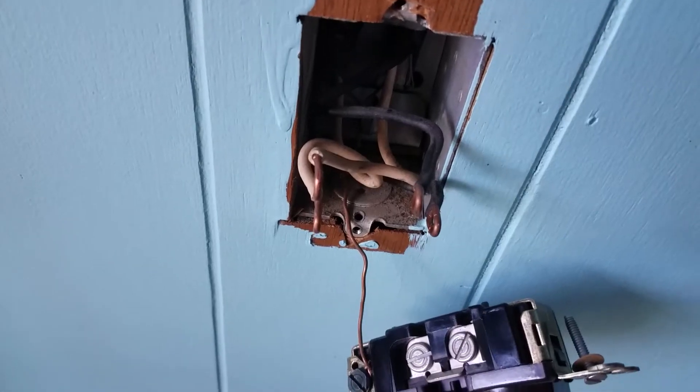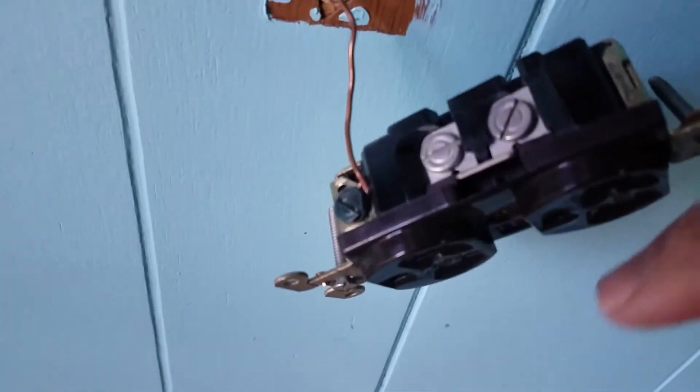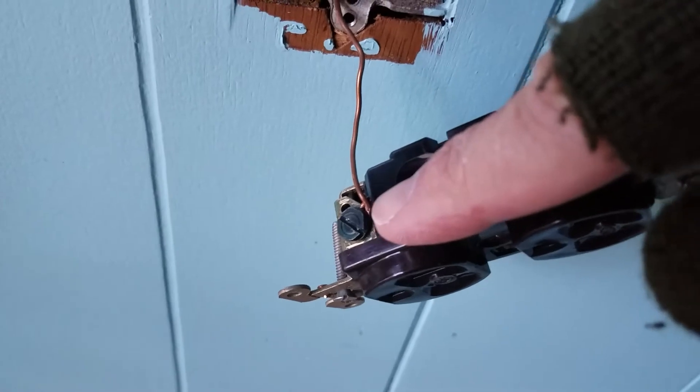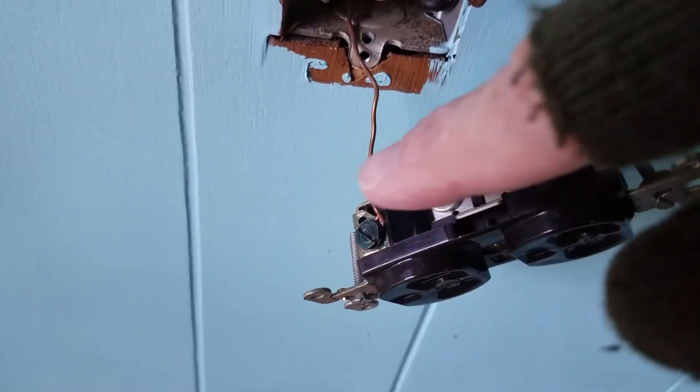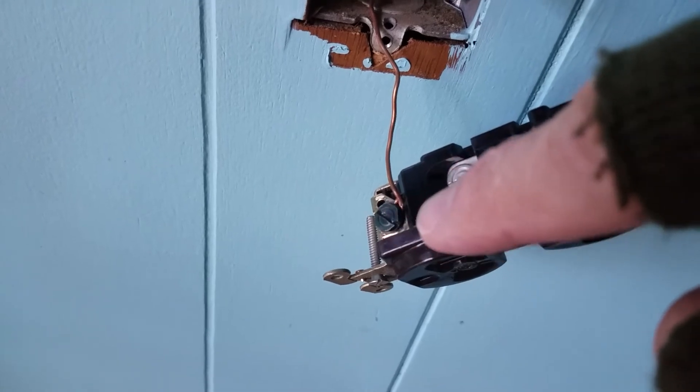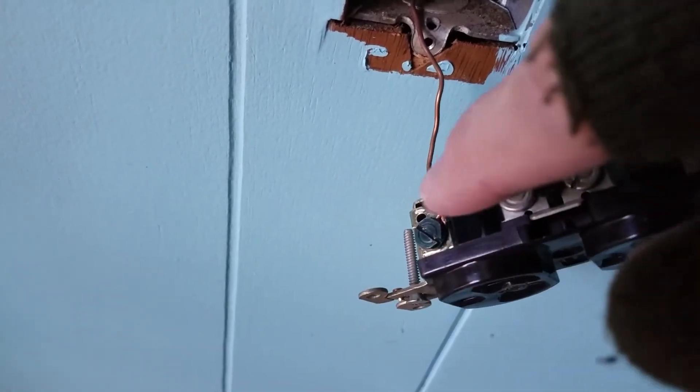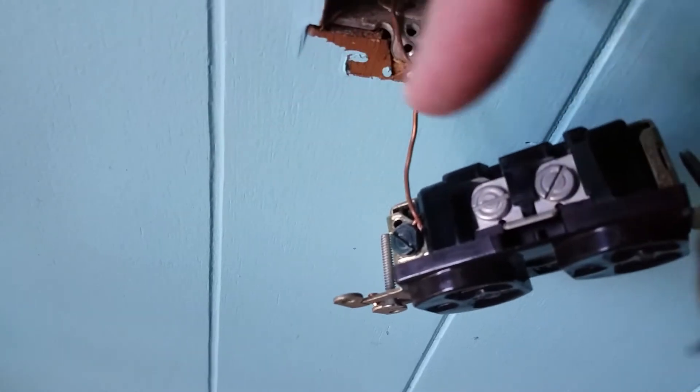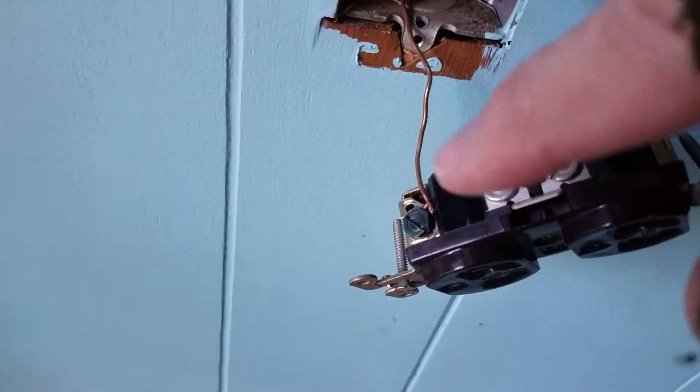Two things I forgot to mention. One, when you attach the wires make sure they go on clockwise because this screw is going to go on clockwise to tighten. So if you wrap the wire the other way counterclockwise, it's just going to loosen up on you.